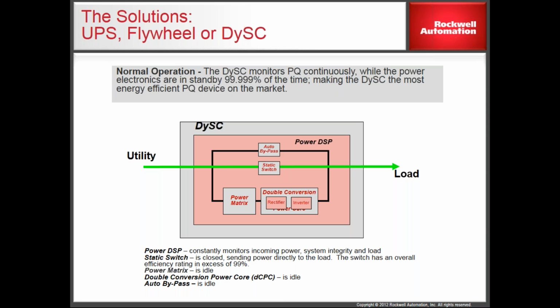The third choice is what we call a DySC. It stands for Dynamic Sag Corrector. That device, and I'm going to explain how it works, is a little different than the other two. That device is going to be able to correct these problems for 5 seconds. So as you look across, all of these have the ability to protect to 0 volts. UPS maybe 15 minutes, flywheel 15 seconds, DySC 5 seconds.